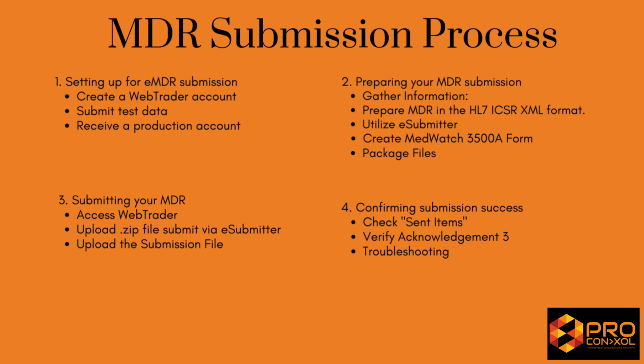Second step is preparing MDR submission, which involves gathering information, preparing MDR in XML format, utilizing eSubmitter to submit that file to FDA, creating a MedWatch 3500A form, and a package files. Step 3 is submitting the MDR, which will be done via a WebTrader account. And step 4 is confirming submission success.